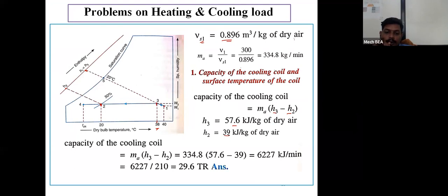Then put those values in the formula of capacity of cooling coil. I will get the capacity of cooling coil in terms of kilojoule per minute, because this value of mass of air I am getting in terms of kg per minute, and values of enthalpy I am getting in terms of kilojoule per kg, so here I'll get that answer in terms of kilojoule per minute. If I want to convert that answer into kilowatt, divide this value by 60, I will get the value in terms of kilowatt. And if I want to have this answer in terms of ton of refrigeration, then divide this answer by 210.